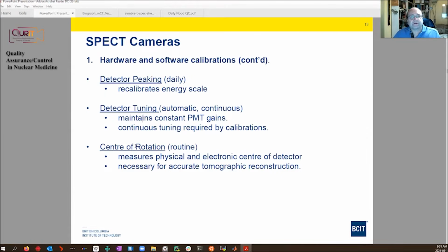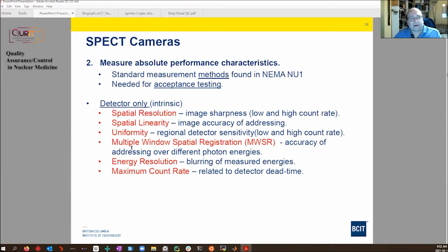Other calibrations are measuring the center of rotation, which is the relationship between the physical center of the orbiting SPECT camera and the center of the image. There has to be an alignment between the center of the orbit, which we call the axis of rotation, and where the center of the detector is. If there's a shift off, it will cause major artifacts in reconstructed images. It doesn't affect planar images, but it is a big problem for tomographic reconstruction. So center of rotation is measured routinely, sometimes monthly, sometimes weekly. In the old days, it had to be done more often, but cameras are more stable now.